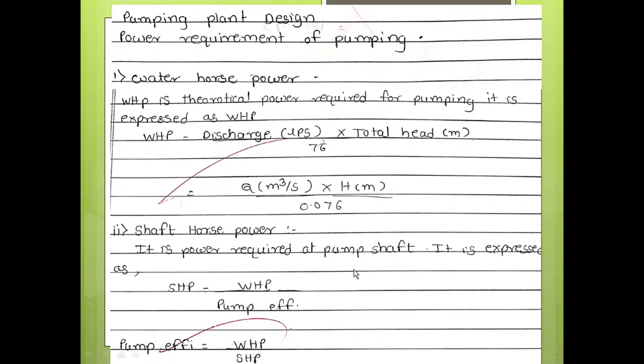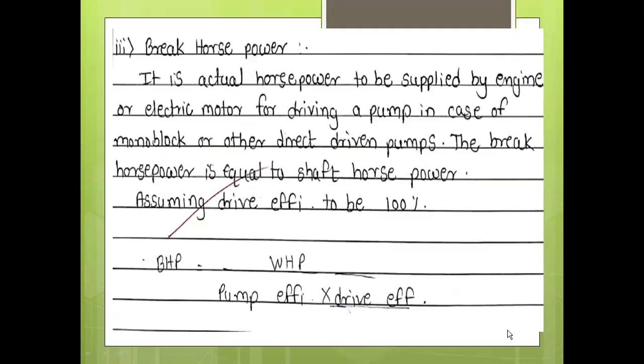Then the shaft horsepower. It is the power required at the pump shaft and it is expressed as SHP, that is shaft horsepower, is equal to water horsepower upon pump efficiency. Therefore, pump efficiency is equal to water horsepower upon shaft horsepower.